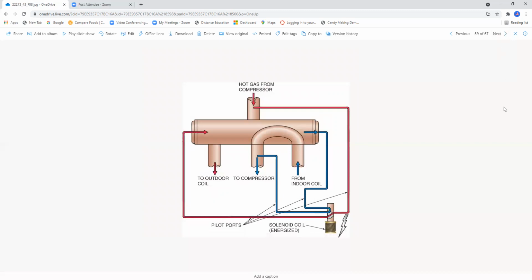Okay, in this particular case, now we have a different situation. The solenoid is energized, so that means we're now in the air conditioning mode. So we're taking hot gas from the compressor. Notice that it goes through the solenoid and basically it goes here to the outdoor coil. That means the outdoor unit is rejecting the heat that was pulled from the indoor coil. So we have refrigerant vapor going to the compressor. And then of course, from the indoor coil, we have the refrigerant, low pressure, low temperature, somewhat superheated vapor entering the compressor down here.